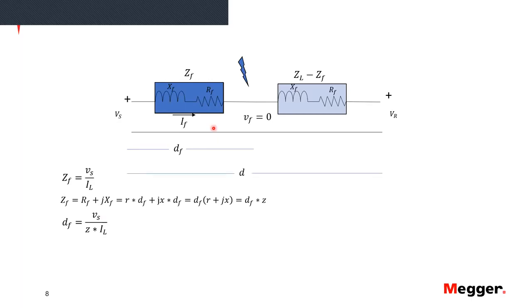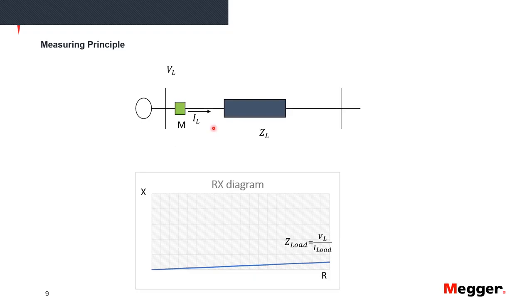So we know then that when we have voltage on a particular line and we have current circulating, if the current that's circulating is because of the load, typically the locus of that, let's say, apparent impedance will be closer to the resistive axis in a resistive and reactive diagram here, because most of the load we try to make circulate in the form of active power. And therefore, we are going to have a high power factor when a lot of load is being transmitted.